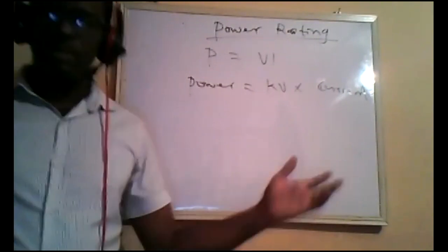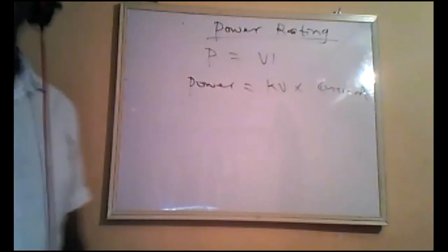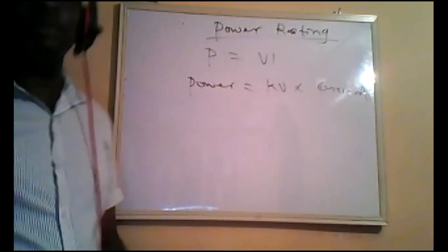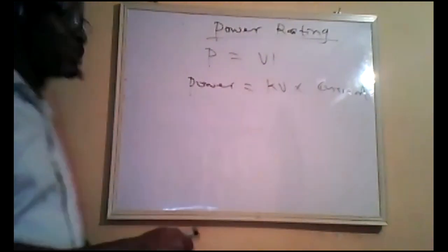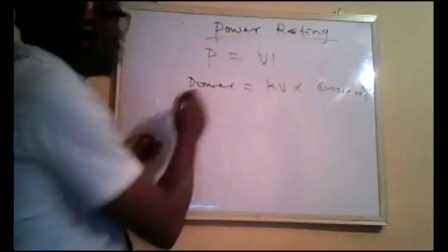You can't just rely on the cooling system of the machine, which uses oil baths, copper attached to the anode, and so on. We have to have our own efficient way of dissemination of heat. So we look at the heat loading.